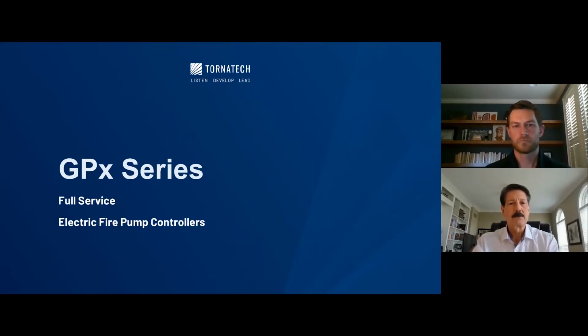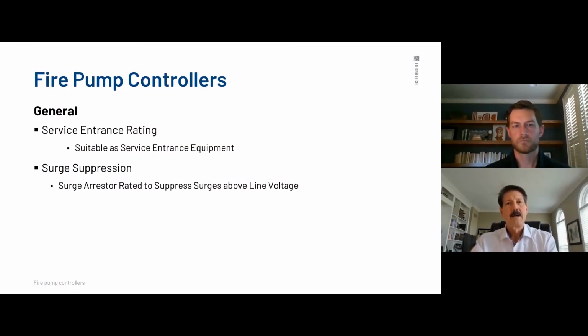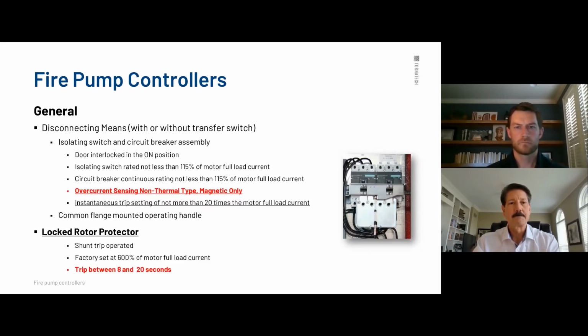Let's get right into the electric controllers, GPx. Again, all fire pump controllers, electric controllers here are service entrance rated, or SUSE, suitable for use as service entrance. They do have a surge suppressor on it. That's required by code. And in general, you see we have a disconnecting means. So this disconnecting means primarily is where you come in, and as you can see right here, as I circle, cabling comes into the ISO switch. It will loop down around into a magnetic only breaker itself. These are typically sized, as you can see, the isolating switch is rated not less than 115% of motor load current itself.